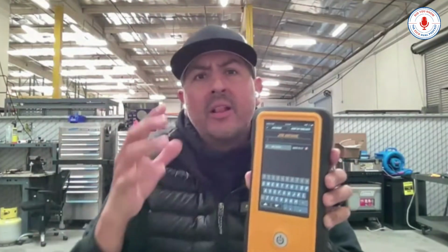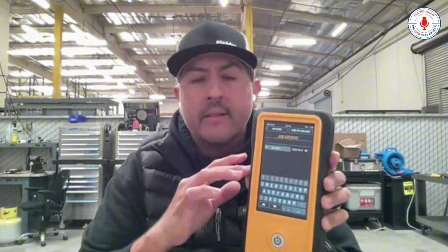So, on the Fieldpiece combustion analyzer, during that warm-up process outside, it is saving the ambient temperature outside as your primary air. Okay. So if you had a 90% furnace where you're pulling in outside air to support the combustion process, there really is no need to update what that temperature is. However, if you're not pulling in outside air and there is a dramatic difference, let's say 15, 20 or so degrees from outside to where the heating appliance is, you might want to consider updating that value to get the most accurate calculations.